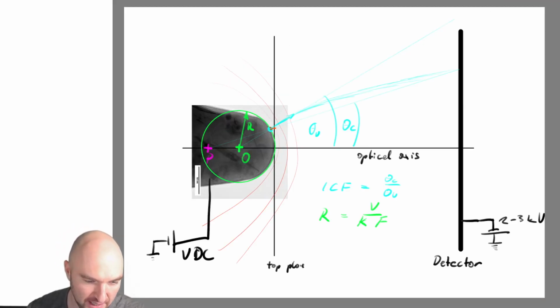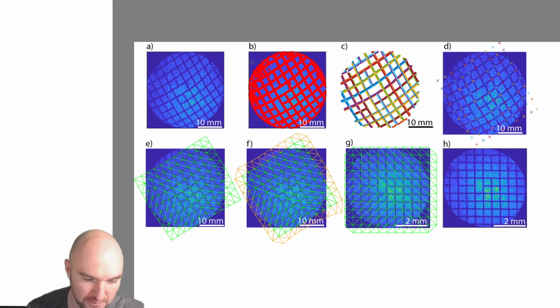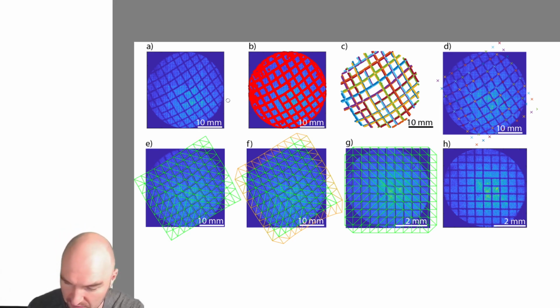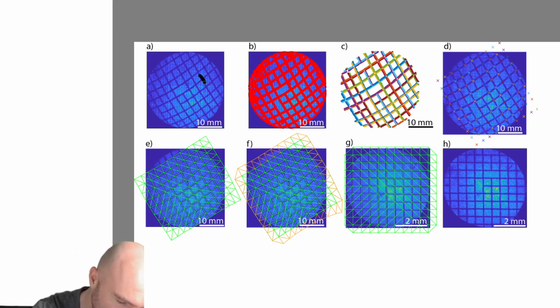I showed you yesterday that the images look quite different for a LEAP 4000 and for a LEAP 5000. We don't have a LEAP 3000 reference data set yet. We'll have one soon. And maybe at some point one of you buys a LEAP 6000 and wants to do that calibration as well, then you can just let us know. And the process is then relatively easy. You just collect some data. Then you outline essentially in the end what we want to know, which is where those intersections are. So we have an algorithm that can outline the intersections and then create a mesh.